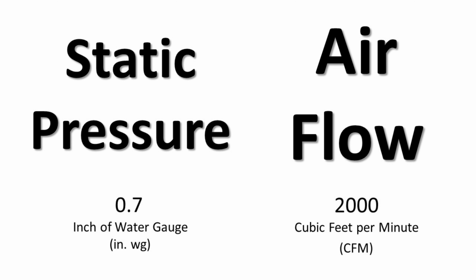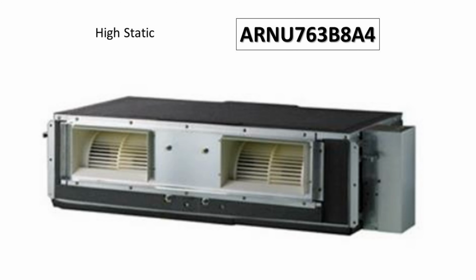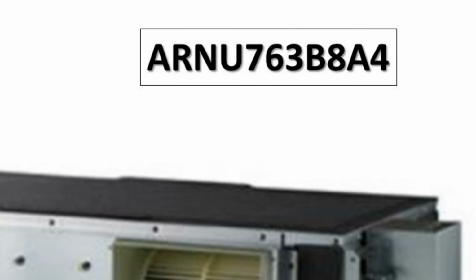In this video, as an example, I will show you how to set up static pressure on a 6-ton ducted type IDU unit. Let's say we've got this information from the engineer, or we designed the ductwork ourselves, and for our ductwork we need 0.7 inches of water gauge static pressure and 2000 CFM of airflow. In this video we will stick to the imperial system of measurement. If you need the metric system, please contact your local LG representatives or convert yourself. Okay, now we have all we need. We have model name, airflow, static pressure, and we're ready to set up ESP.